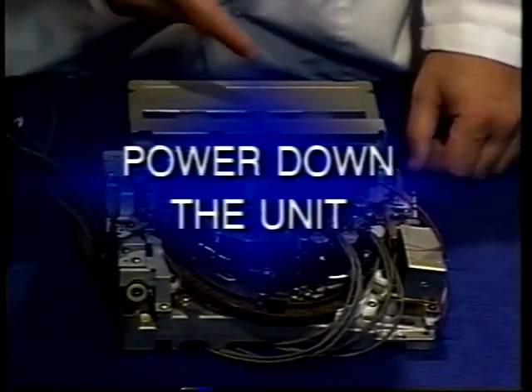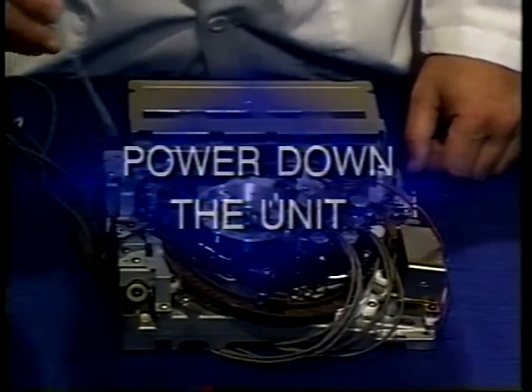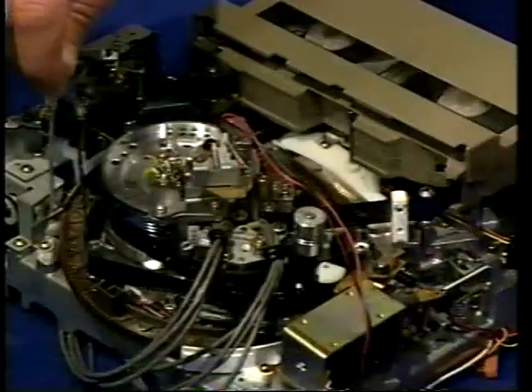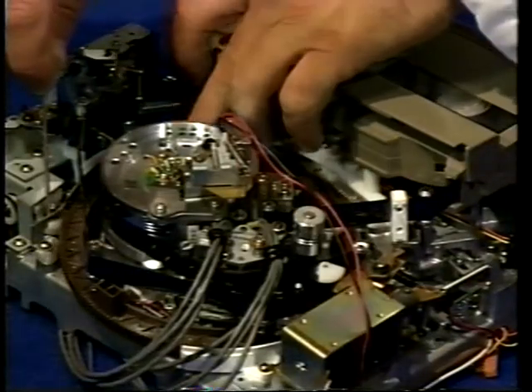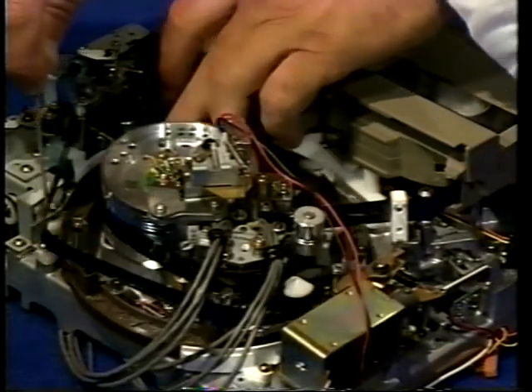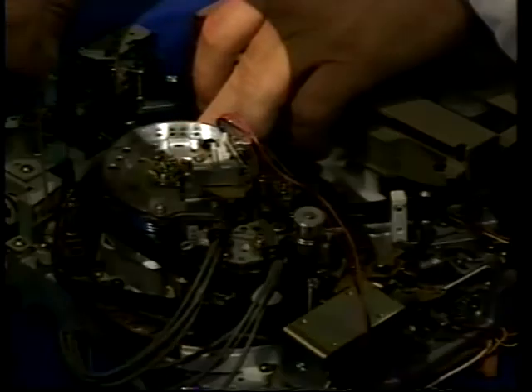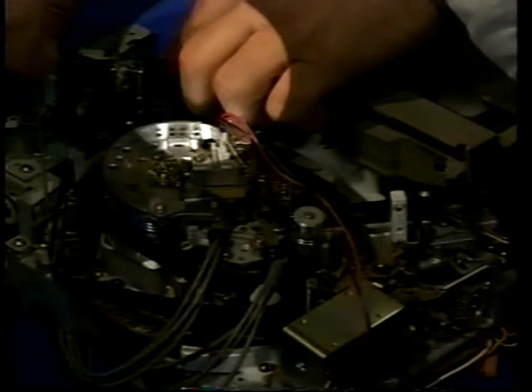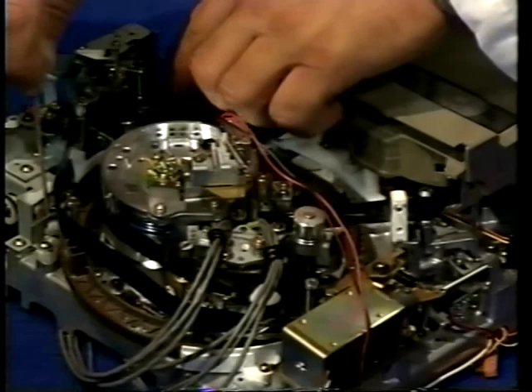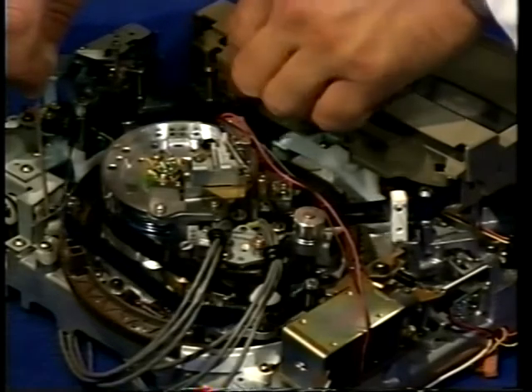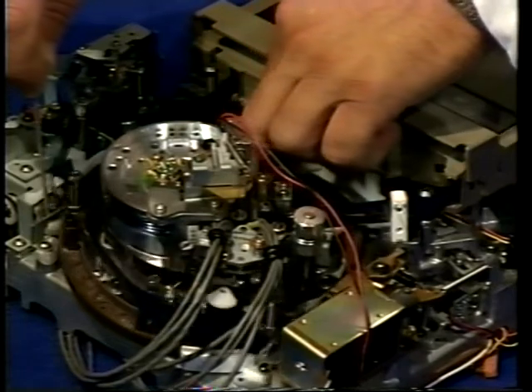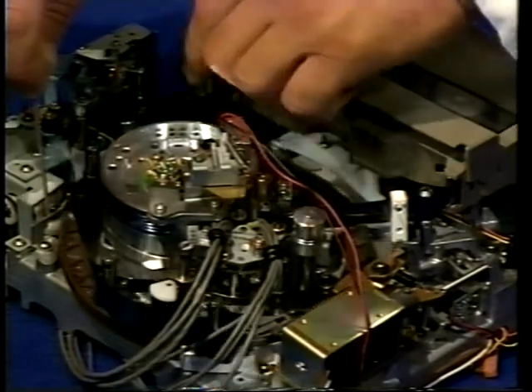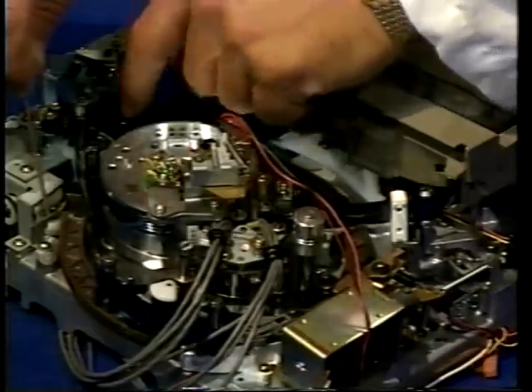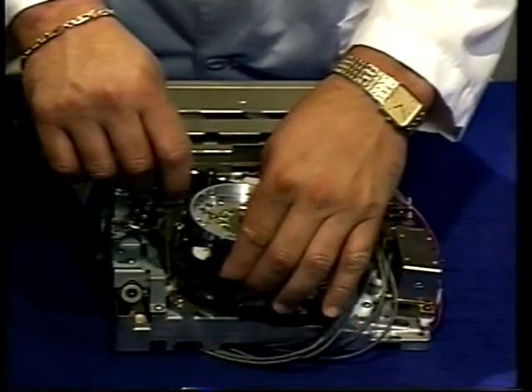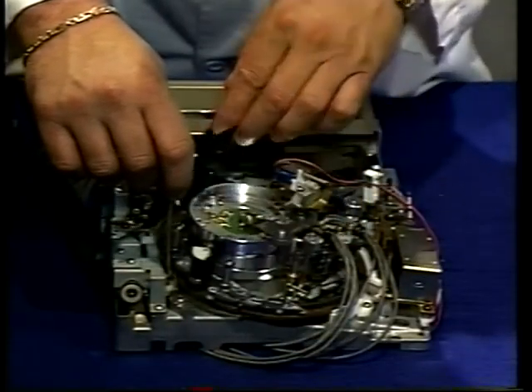Emergency tape removal is done with the power off. Push down on the loading ring and start to turn the loading gear in a clockwise direction. Take up the slack in the tape by pulling it along here, being careful to handle the tape only by the edges. Alternate turning the loading gear and taking up slack in the tape as shown here. At this point, we can lift the tape off and curl it out of the way.